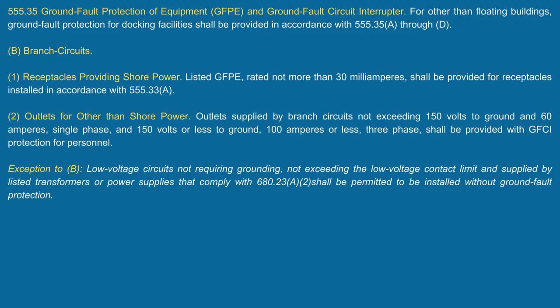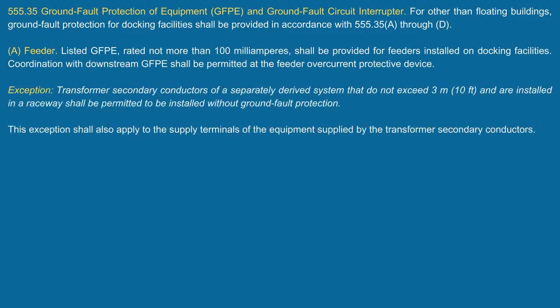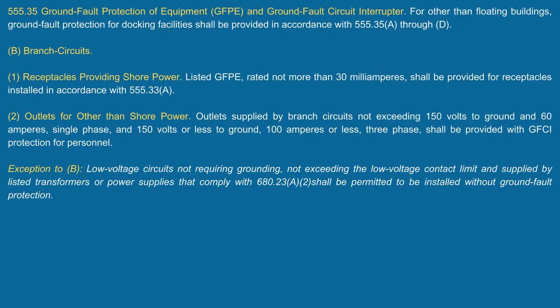And if I go back and look at 555.35(A), it says it will not be rated more than what? 100 milliamps. So that ties into what you were just saying. Yeah, there are devices out there that you can dial from 100 down to 30, and he was saying you could dial them down to 4 to 6, but I've already run this through with some pretty top people in the industry, and they basically say that just because that device can dial down to 4 to 6, that does not make it a Class A device. That's still a Class E device for equipment, regardless of whether you could dial it down to 4 to 6. Sure. It doesn't change to a Class A device.